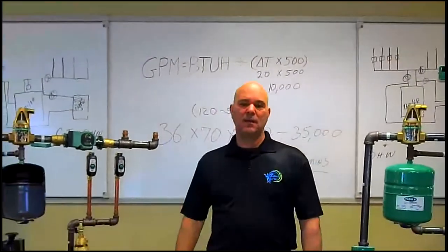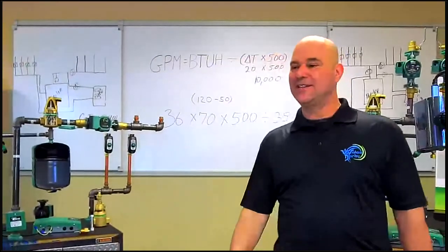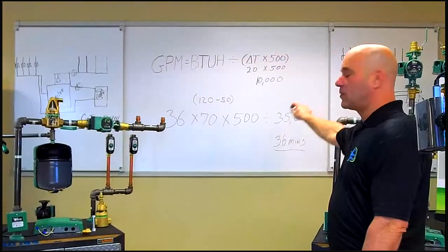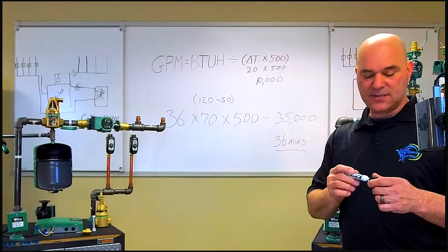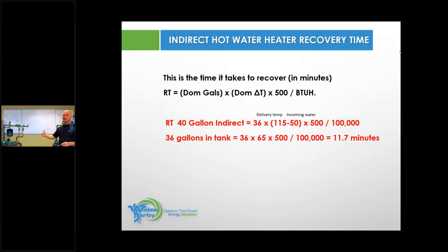And you're going to say, man, that's a terrible indirect. But reality is, it's what we're driving it with. And this is a formula that you can use in the field to make sure that when the homeowner is complaining of insufficient hot water, or after we take two showers, we have no hot water, this is something to look at when you go in there and try to figure out what's the root cause of the no hot water situation. Okay, so that is recovery time formula.